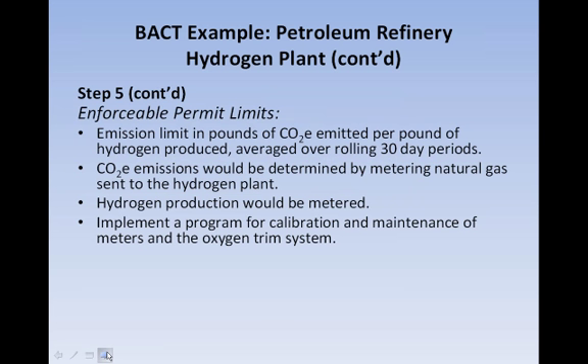The permitting authority determined that BACT would be enforced through the following set of permit conditions. There would be an emissions limit in pounds of CO2e emitted per pound of hydrogen produced, averaged over rolling 30-day periods. The CO2e emissions would be determined by metering the natural gas sent to the hydrogen plant. The hydrogen production would also be metered. And then finally, there would be a need to implement a program for calibration and maintenance of the meters and oxygen trim system.